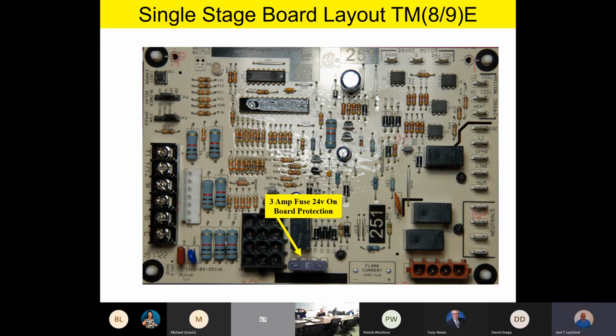We move around the board, and we have a 3 amp fuse for 24 volt onboard protection. This is just a cartridge, automotive type fuse, and those are typically 3 to 5 amp fuses on the board. Right next to the fuse, we have a 12-pin harness. This will be harnessed in from the factory, but if you remove that harness, you'll see there are actually 12 pins. This harness gives us our inputs and outputs to things like our gas valve. Our safety circuits will all be harnessed in on this 12-pin harness.